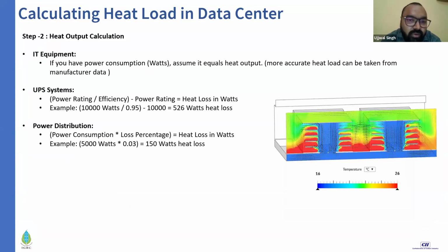For the UPS system, you can simply take the power rating divided by the efficiency. So if your UPS is consuming 10,000 watts at max and your efficiency is 95%, then you get a heat loss of 526 watts of total heat loss.